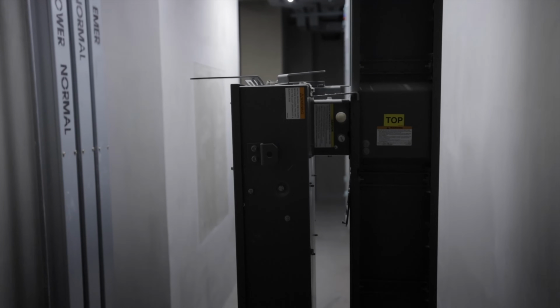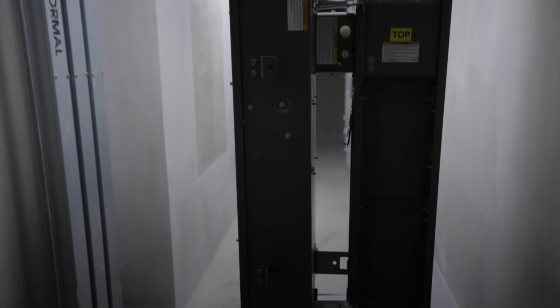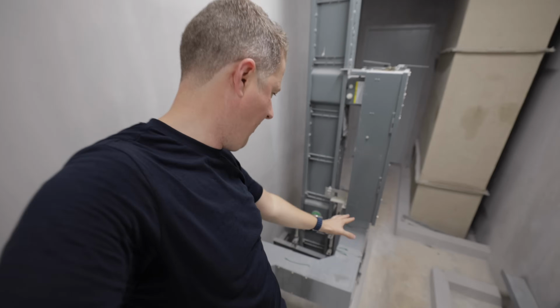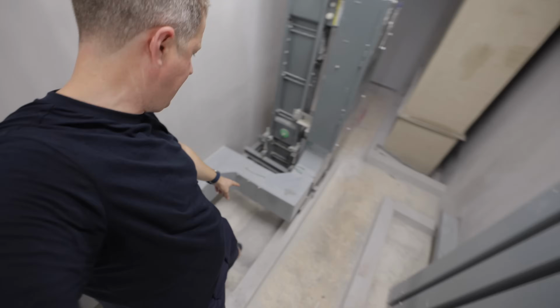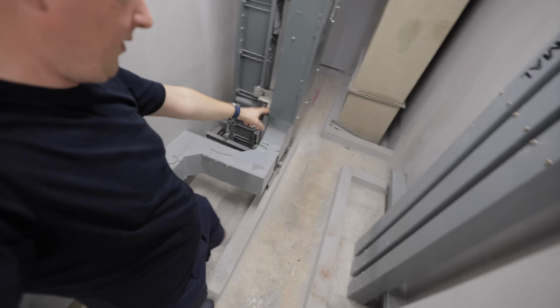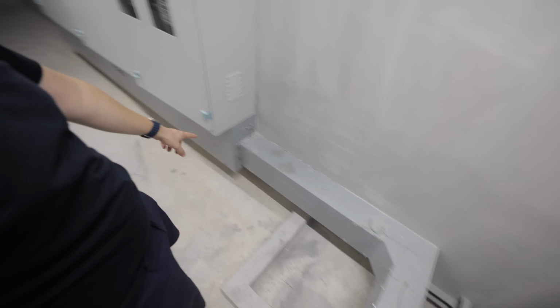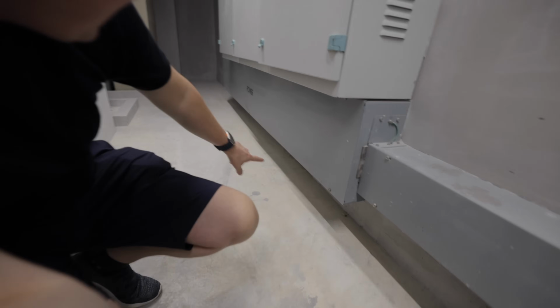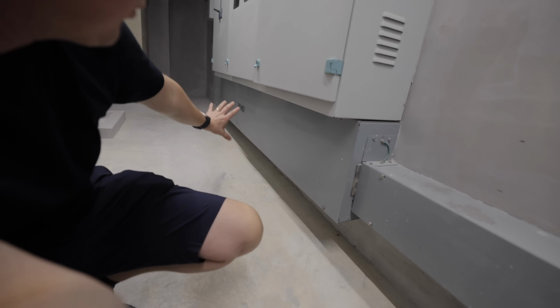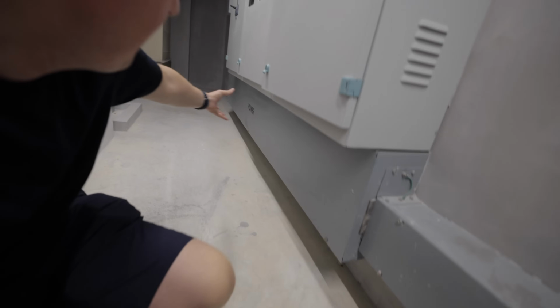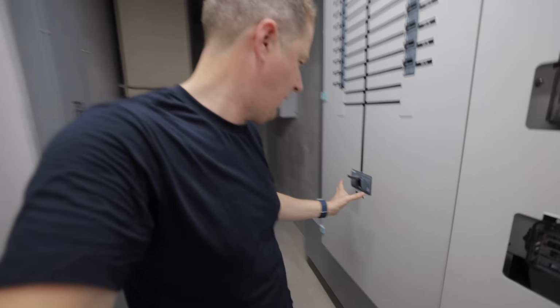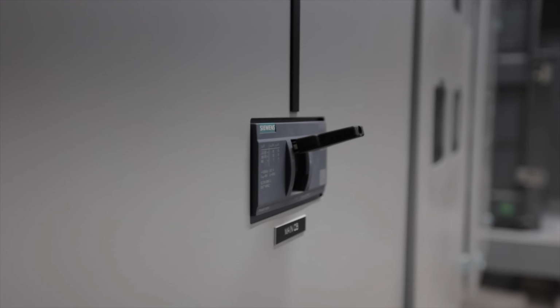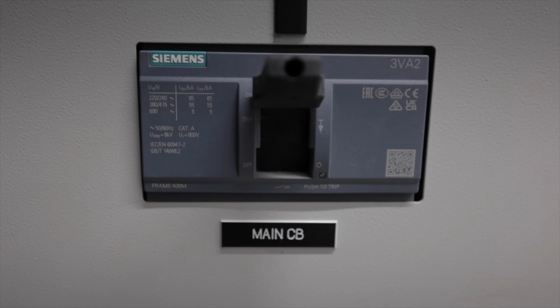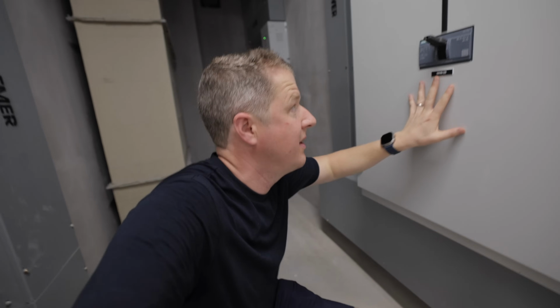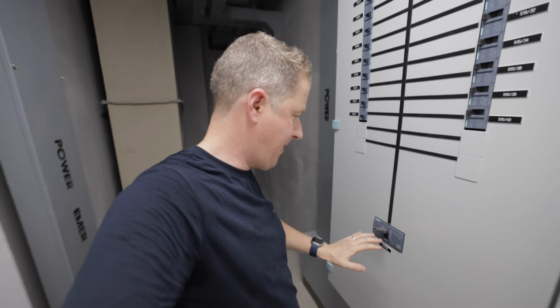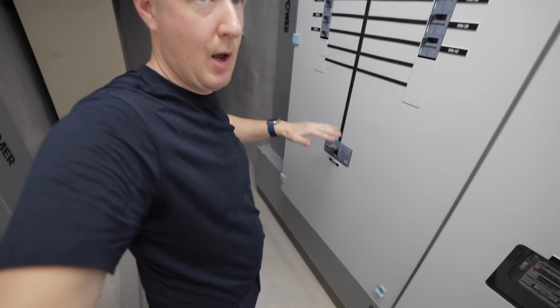Essentially, it's got massive rails of thick copper in there, presumably copper, and off of those we tap with this thing. This enables us to isolate this trunking down here, and presumably in this trunking there are various thick copper wires that go along and under into here. This is an open piece of trunking, and from that those wires go up into this main switch, the main switch or circuit breaker for this entire floor. That cable from the bus bar feeds into the bottom of this circuit breaker, then out of this main circuit breaker or main switch, which would turn off this whole floor.